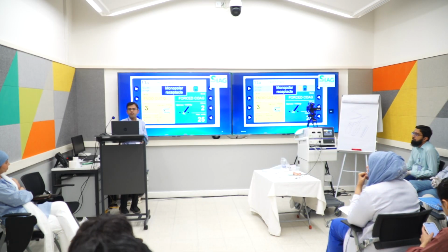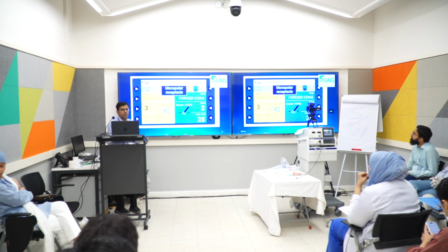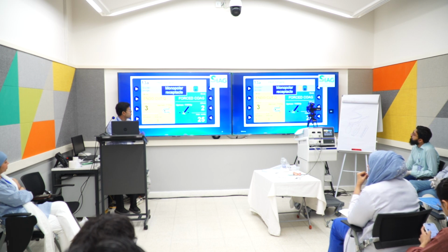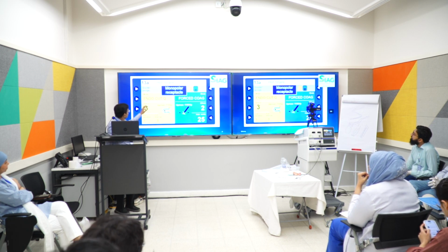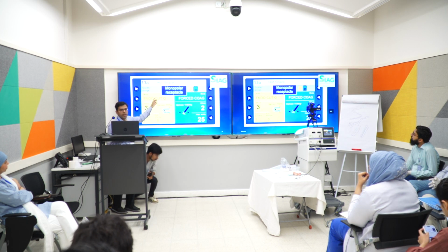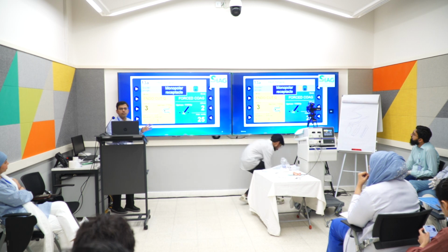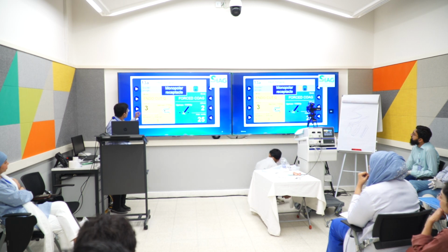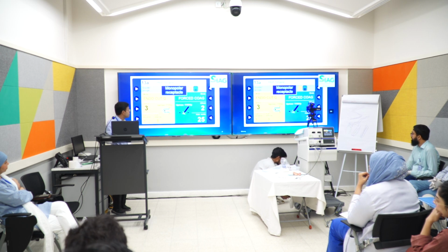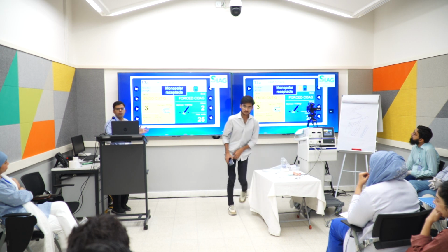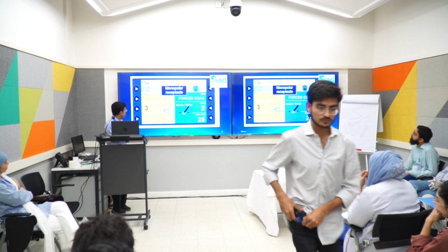So this is the screen of an ERBE electrosurgical unit. As most of us are moving towards ERBE, it's important to understand. It has two modes. The Q mode is used for snare, and the I mode is used for sphincterotome. Effect means the degree of coagulation involved. There are 4 levels. If we move to 4, there is more coagulation. If we move to 1, it's usually a pure cut, and blended currents in between.